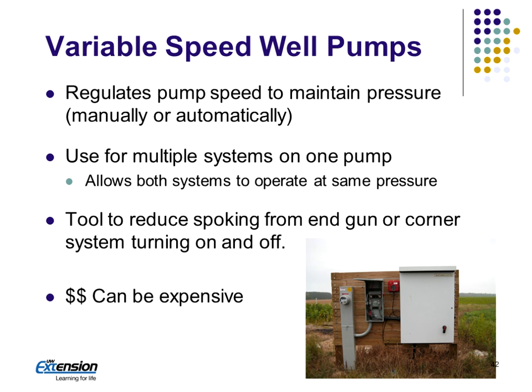Variable speed controls on well pumps have become more cost effective because the cost of the variable speed drives has come down. Basically we can regulate the pump speed to maintain a pressure. We can do this either manually or automatically. If we did it automatically, we'd have a pressure transducer that would speed up and slow down the pump to run at a maximum or a set pressure.